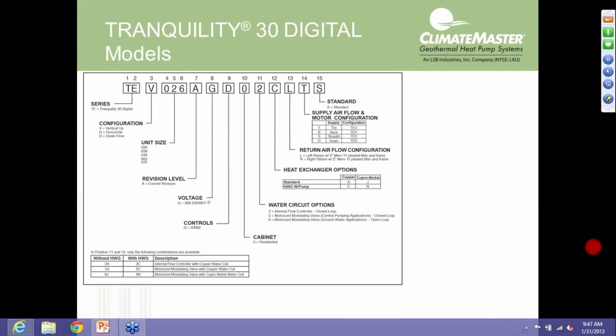Let's look a little bit now at the breakdown in the model number nomenclature, and one of the big points I want to point out is the water circuit options. In these digital units, the only option is either a modulating valve or a built-in variable speed pump. Now, the modulating valve comes in 2 forms, either a closed loop version or an open loop version. And the two should never be interchanged. The valves are drastically different between the two.